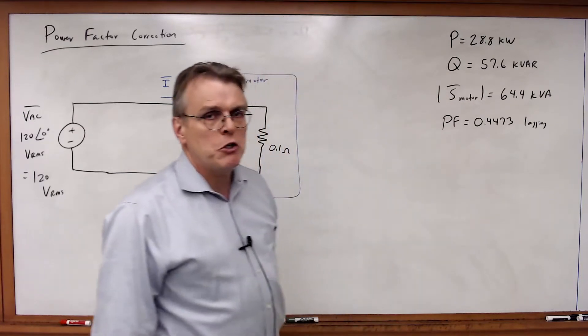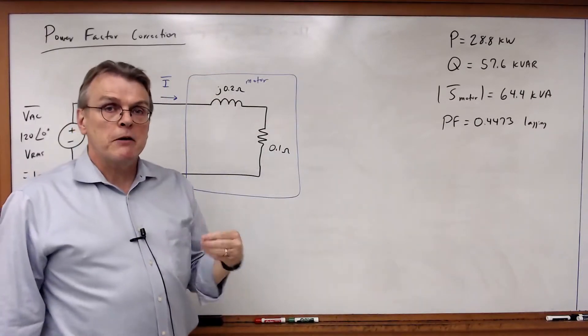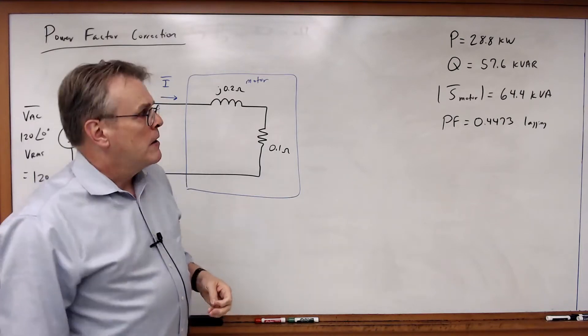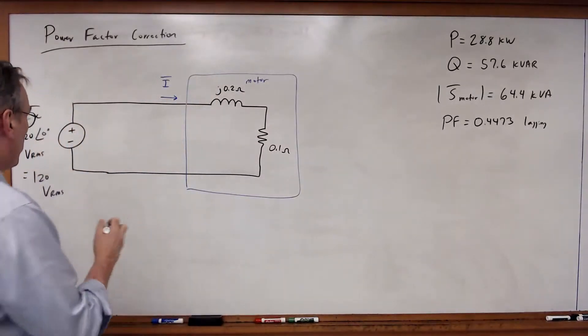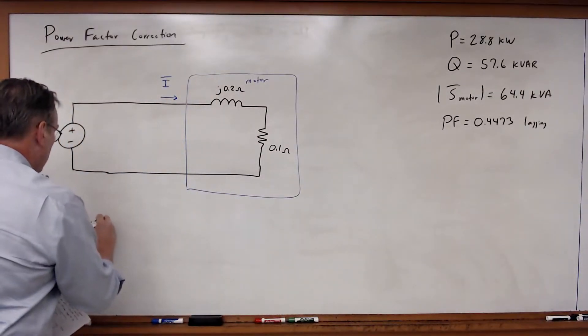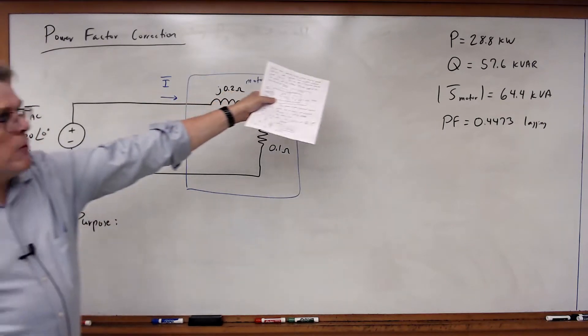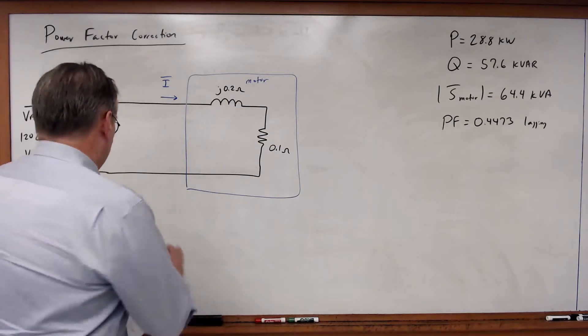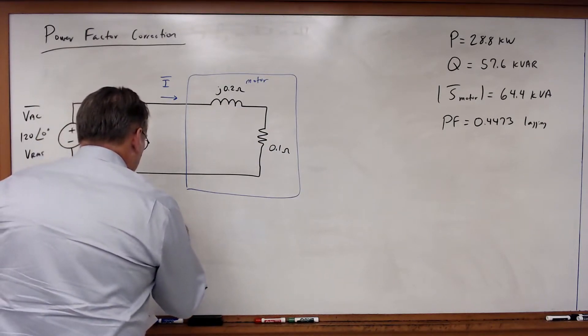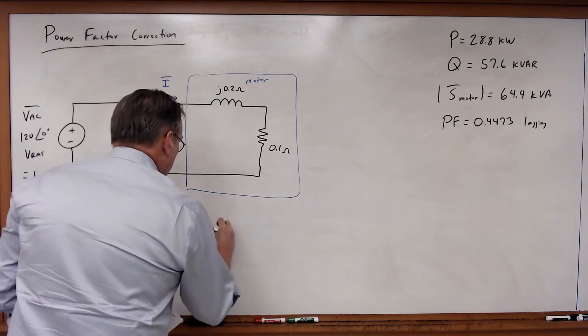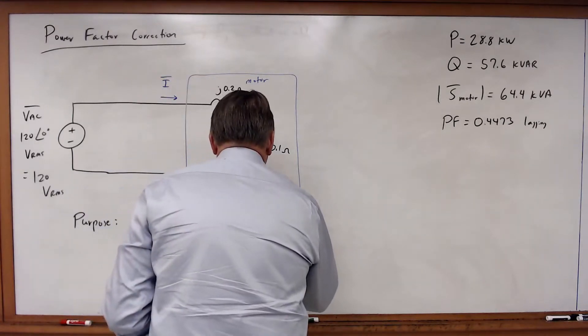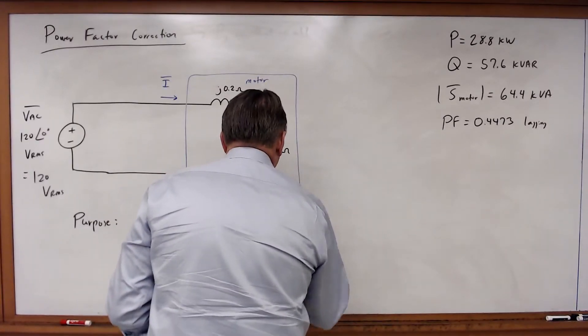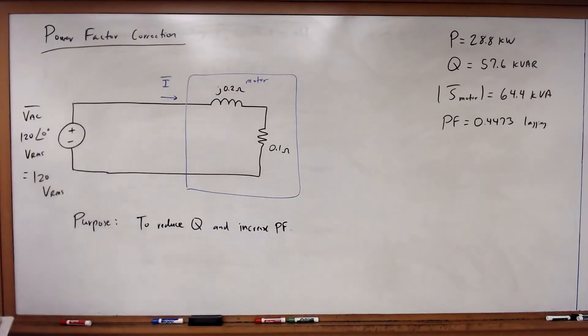In other words, you have too much Q, too much reactive power, because they need to make their generators bigger to supply that reactive power. The answer is power factor correction. The purpose of power factor correction is to lower the Q of your load and thereby to increase the power factor. It turns out it's a pretty simple process requiring one additional component.